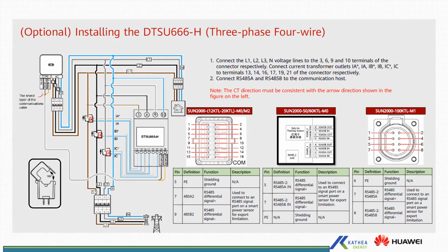For the DTSU, it's not mandatory to have a resistor. Then you just wire the RS-485 A and B either to your inverter or to the logger. So this is basically the schematic of it, and then these are different pin settings to connect your meter. For all the inverters, the meter is connected on RS-485 2, whether it's a 100 KTL, a 50-60, a 12 to 20, or a 36 KTL range.